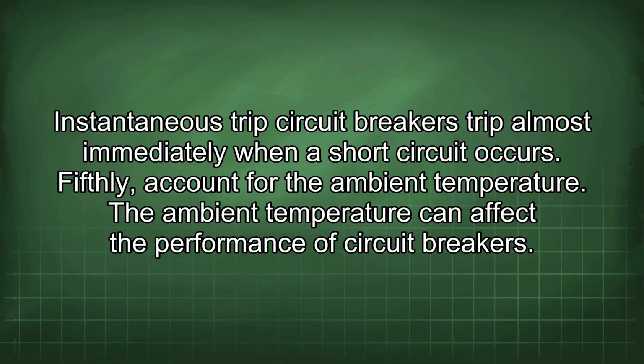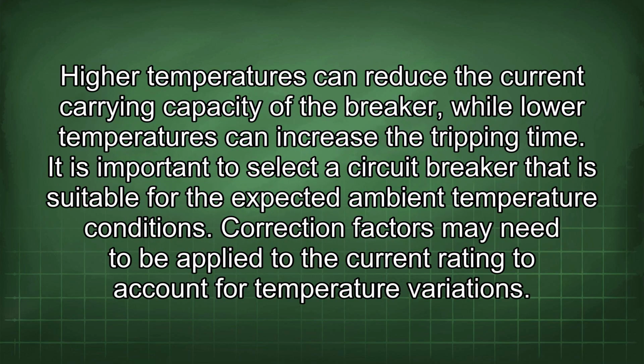Fifthly, account for the ambient temperature. The ambient temperature can affect the performance of circuit breakers. Higher temperatures can reduce the current carrying capacity of the breaker, while lower temperatures can increase the tripping time. It is important to select a circuit breaker that is suitable for the expected ambient temperature conditions. Correction factors may need to be applied to the current rating to account for temperature variations.